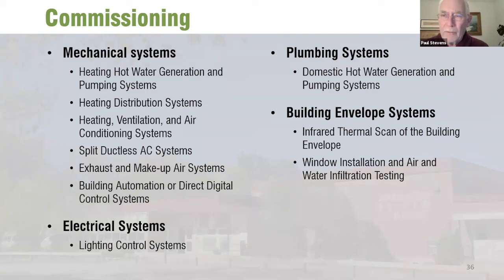This is an obvious example from a number of years ago, with a high school I designed. A few months into the winter, we couldn't figure out why the heating costs were so high—it didn't make sense based on our estimates. We discovered that someone had miswired the ventilation system for the gymnasium, a huge gym, and it was exhausting all the heated air out all winter long. If we'd had commissioning, that would have been discovered before the school opened. That's just one small example of what you can catch when verifying the system before startup. It's a very important thing to do these days.